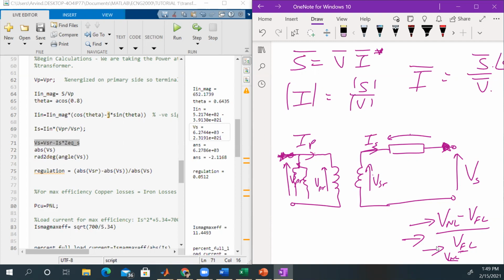So usually the output voltage is the important thing. You don't care what voltage the generating station generates. What you care about is what voltage you get at home. And the way you get that to be within a particular limit, at the voltage you need, is by the utility adjusting taps on the transformers. The transformer taps effectively change the turns ratio of the transformer. So the more you load the transformer, the more you're going to get voltage drops here, voltage drops on your lines and so on.